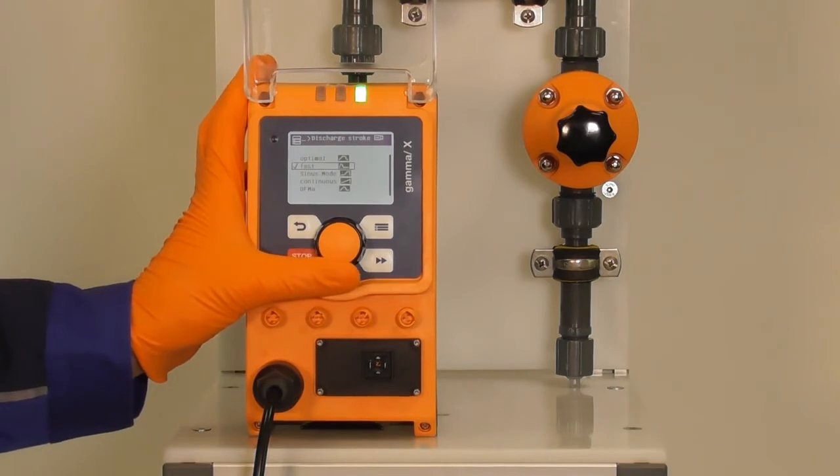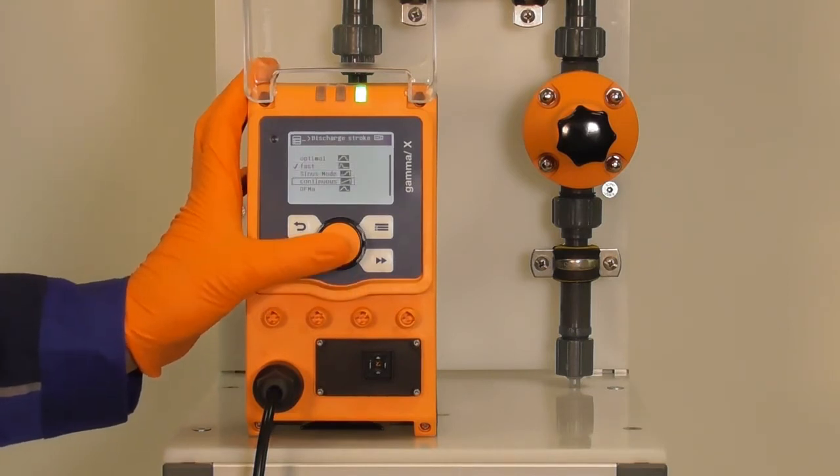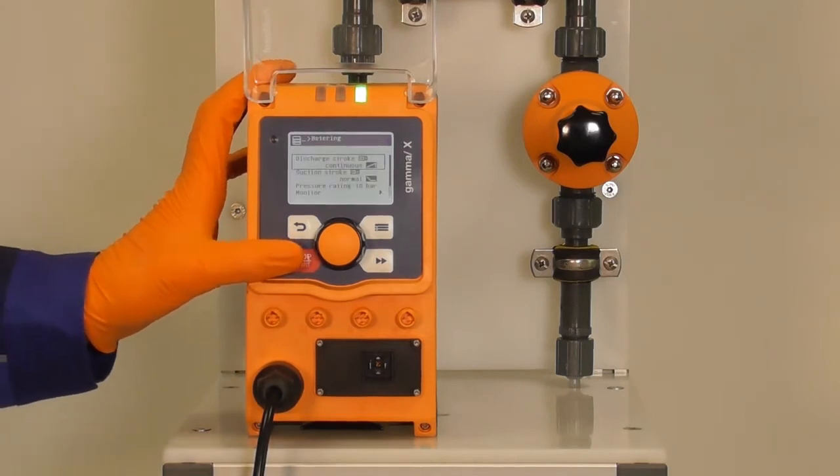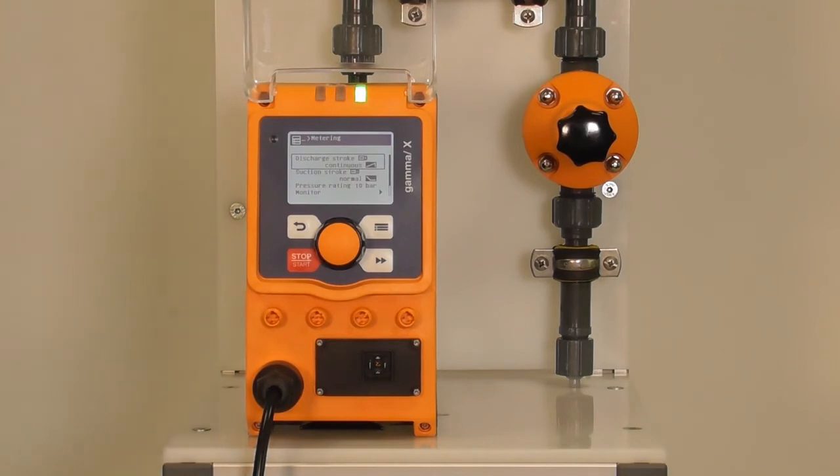Next to fast we have continuous which is also really common and used by many customers. In continuous mode the pump is dosing as continuous as possible. Depending on the stroke frequency the dosing profile can last up to 3 minutes.